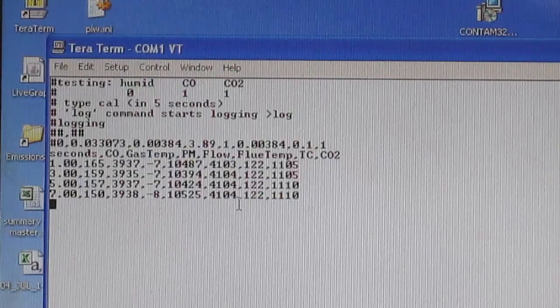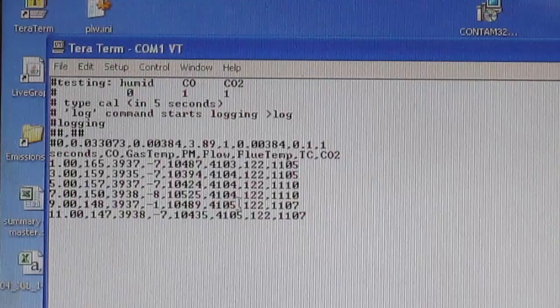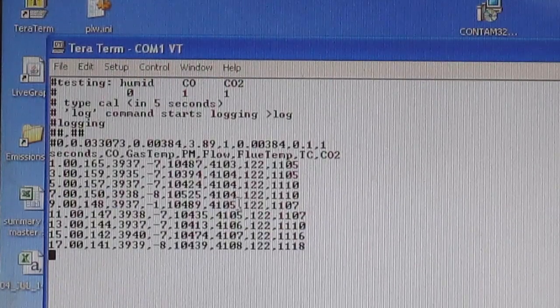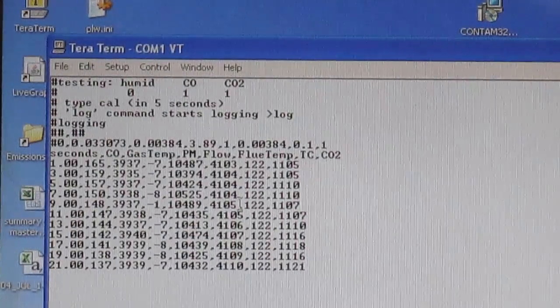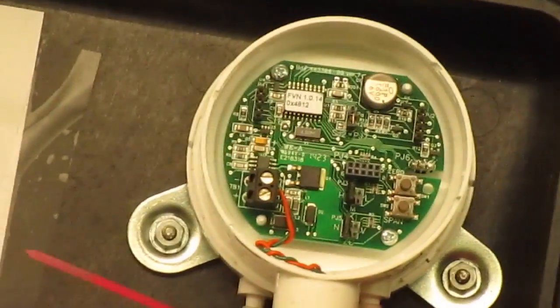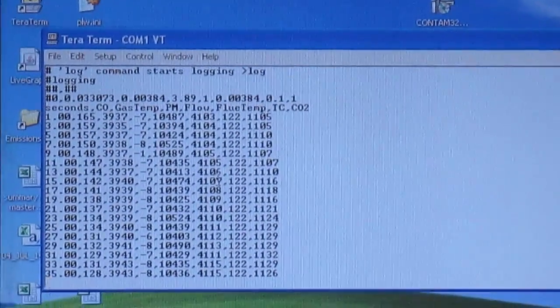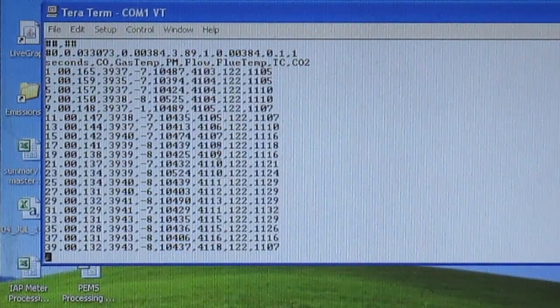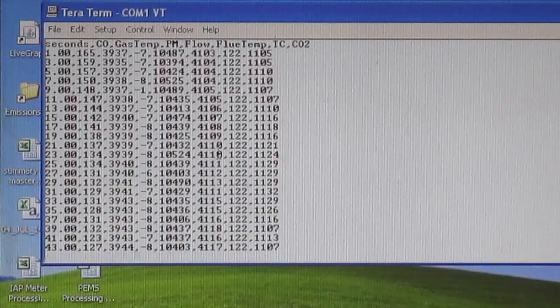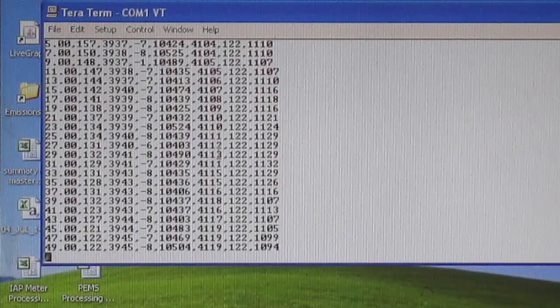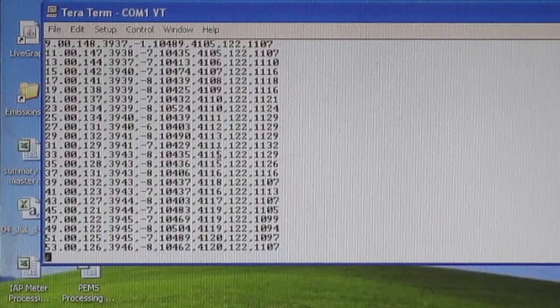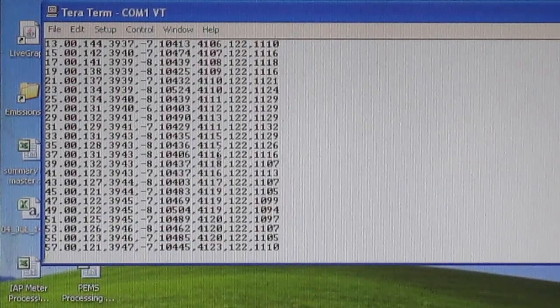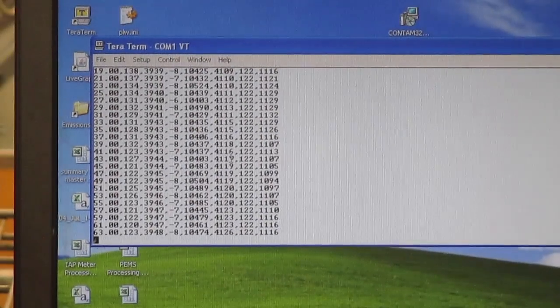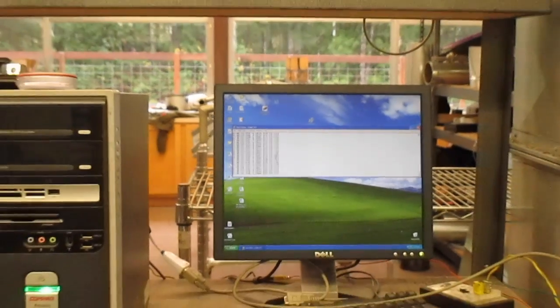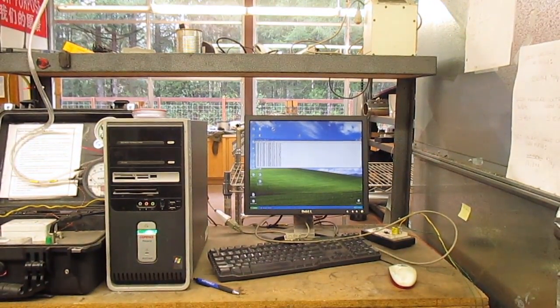What we're going to do is go just the simple procedure to zero the flow sensor. It's not going to do anything because I've done it recently, but this is all you have to do. I've already opened up the sensor head, so I'll just push that button for 4 or 5 seconds, and we'll see if that zero reading, if that column 5 changes at all. 1, 2, 3, 4, 5. I didn't see any change, but that's because it's already zeroed. That's the process though. The blower has to be turned off. There's no airflow through the room. So make sure you're getting an actual zero. That's the process to zero it.